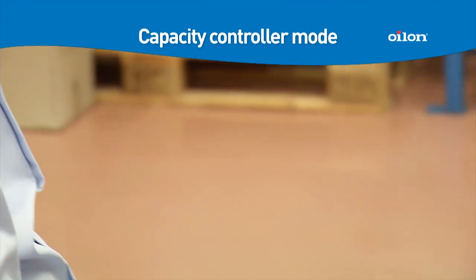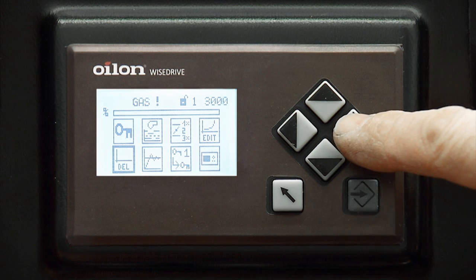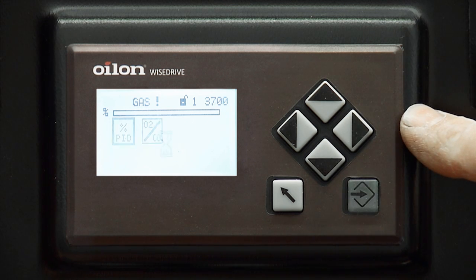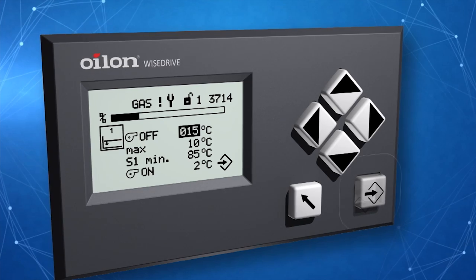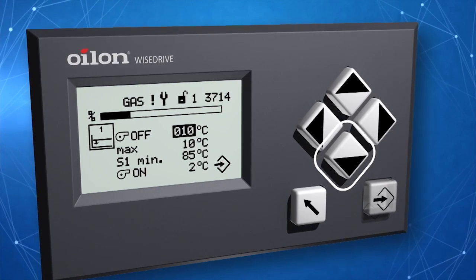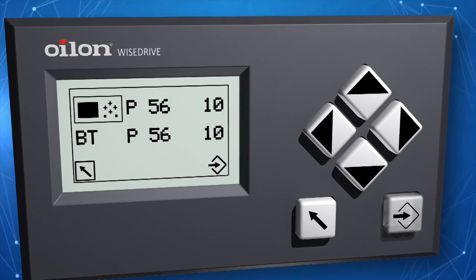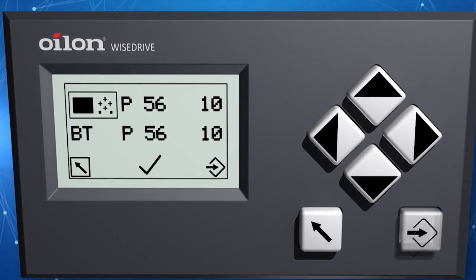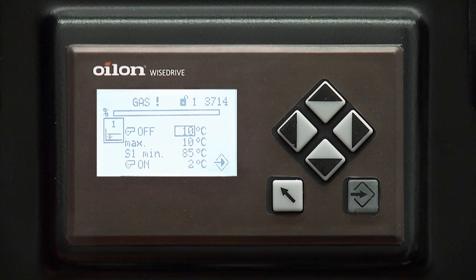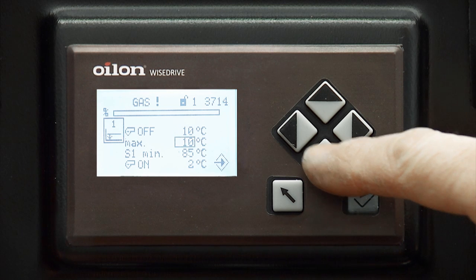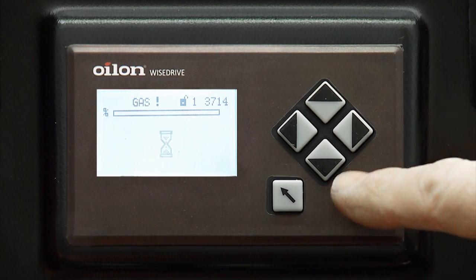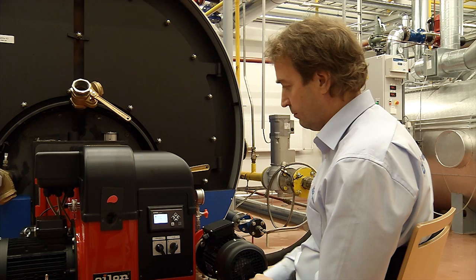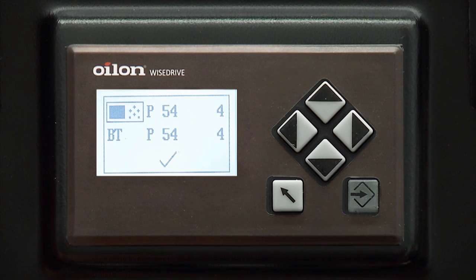When the burner adjustments have been made, it's time to set the boiler operating temperature or pressure. After that, you need to set the on and off operating limits. Enter the PID menu and set the boiler temperature or pressure limit values. The preset option for the capacity controller in the burner control is automatic. Depending on the burner and boiler conditions, you might need to change this to atmospheric conditions or external firing rate input. For more information, refer to the manual.